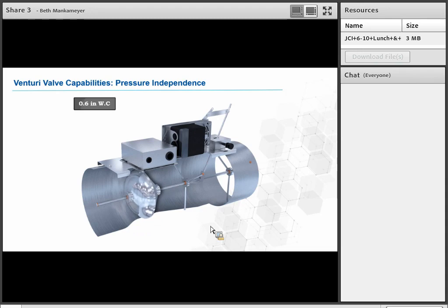So in this example, the CFM would stay the same. So call out a CFM number, let's say 500 CFM. It would be 500 CFM the entire time that this cone is moving. It's just moving with pressure changes within that valve.